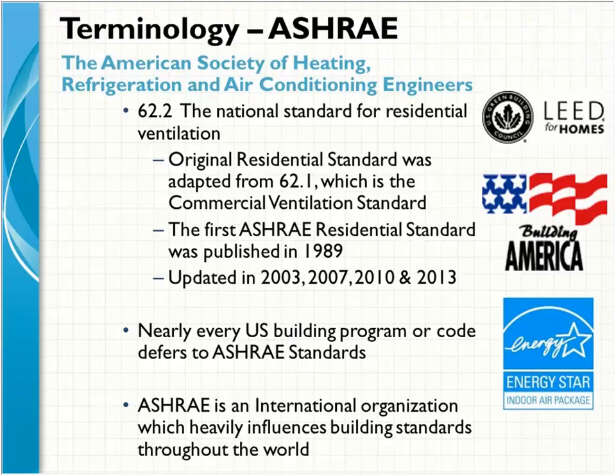But the numbers will end up being the same. Across the country, you'll have many different programs: Building America, LEED for Homes, Energy Star, American Lung Association, Healthy House. Each of those programs will defer to ASHRAE 62.2 for their ventilation code. They don't create their own ventilation code. They refer to ASHRAE 62.2, or the calculations or the chart within ASHRAE 62.2, rather than trying to design their own standards.